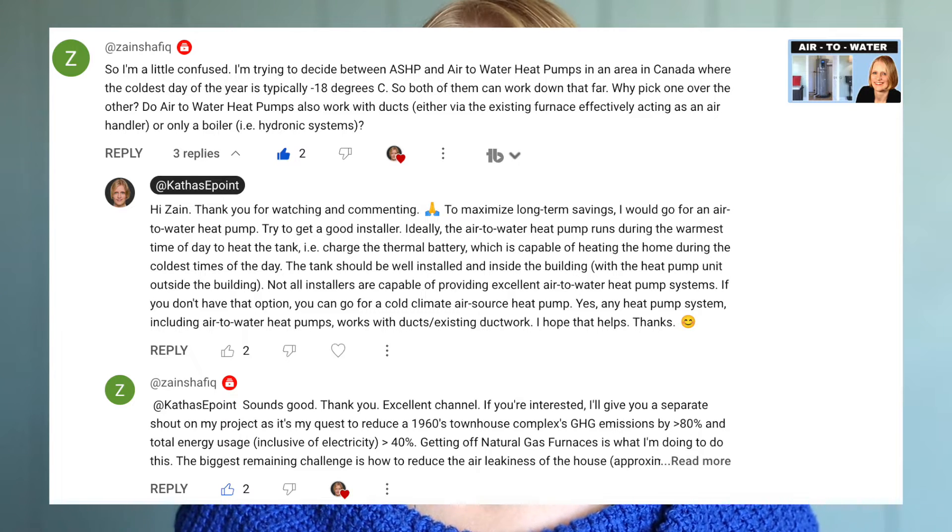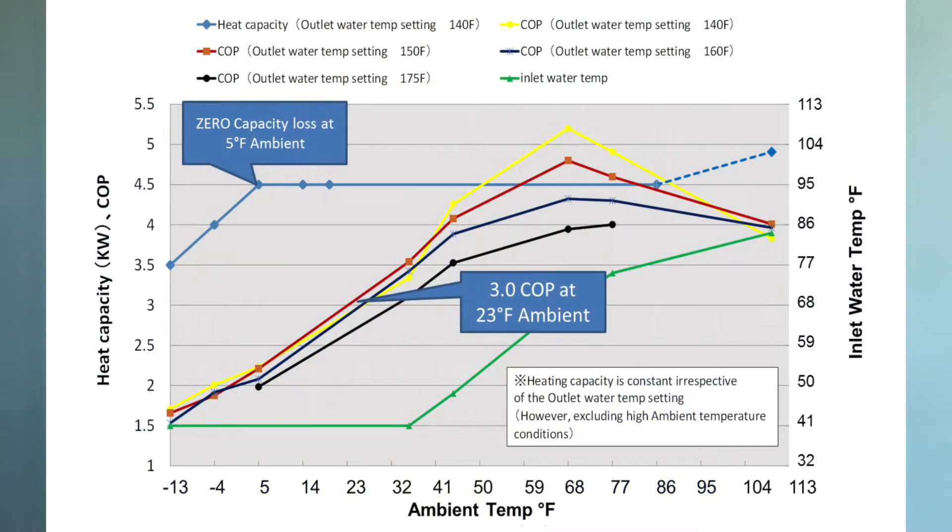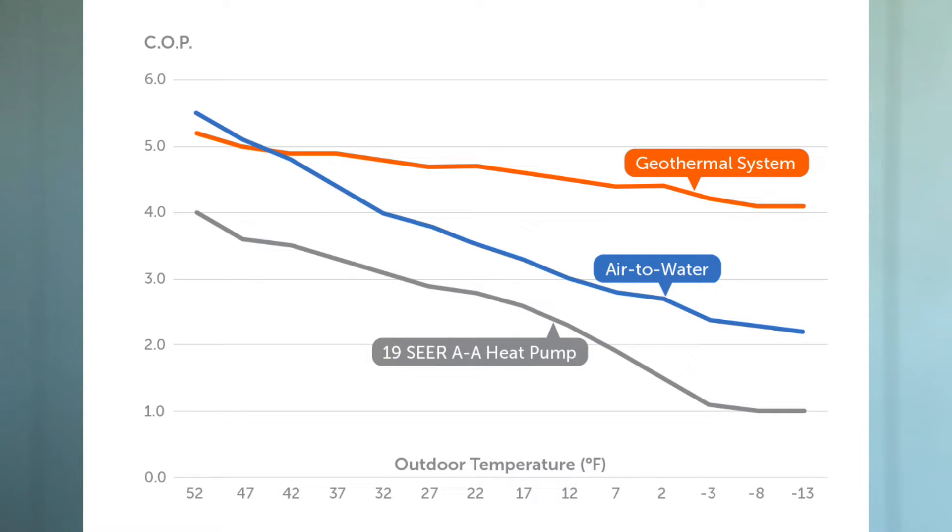One viewer asked: I'm trying to decide between an air-source heat pump and an air-to-water heat pump system in Canada, where the coldest day of the year is typically minus 18 degrees centigrade. So both can work down that far — why pick one over the other? Do air-to-water heat pumps also work with ducts? There are several questions here. Outside temperature is a big part of the decision when it comes to air-to-water versus geothermal. However, there has been a lot of development in cold-climate heat pumps, resulting in much more efficient systems at low outside temperatures. The coefficient of performance depends on the load-side inlet temperature, which you need between roughly 35 and 45 degrees centigrade (95 to 113 Fahrenheit). If we look at minus 25 centigrade or minus 13 Fahrenheit, the COP is still around 2 — meaning 200% efficiency. When we feel freezing cold outside, it's hard to imagine how much heat there is still in the air.